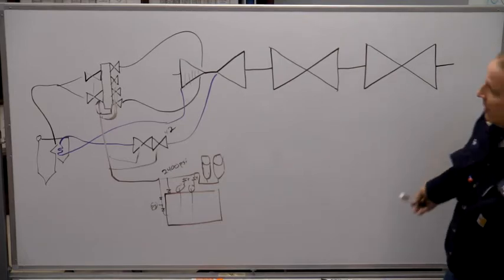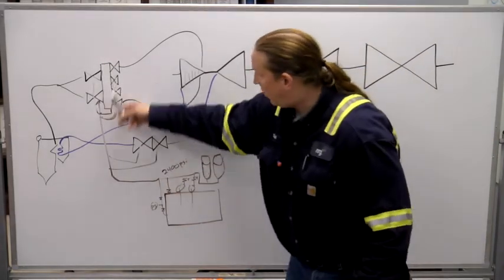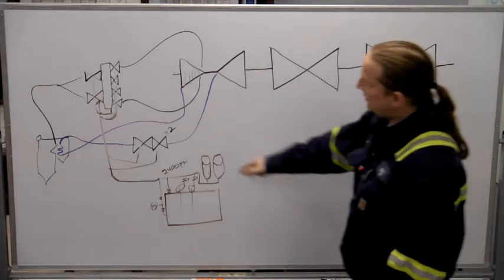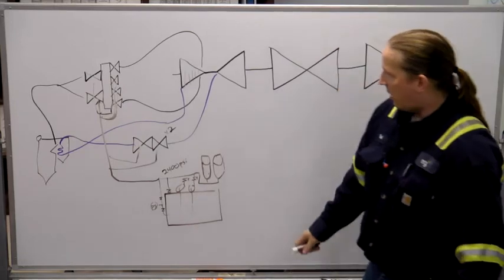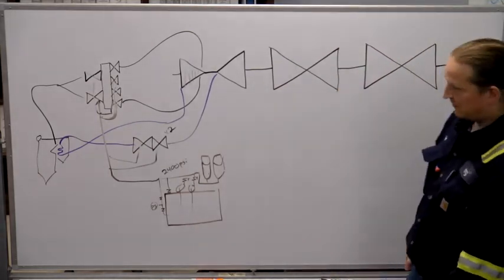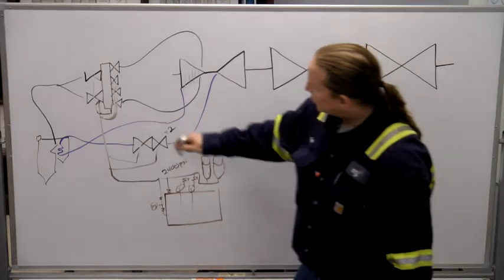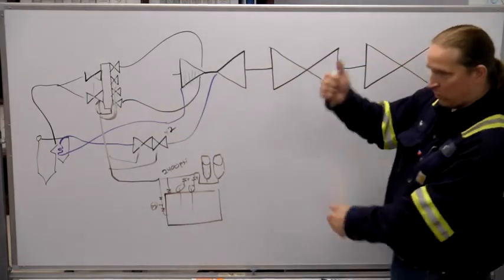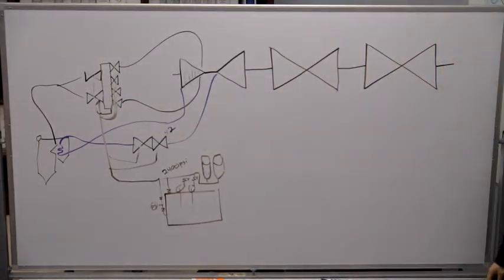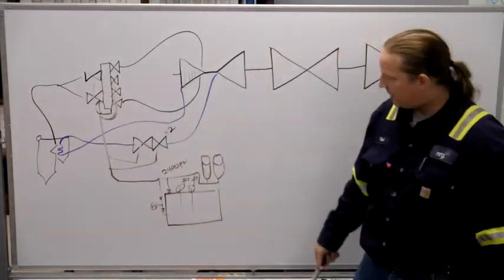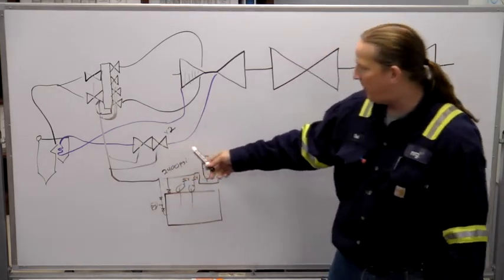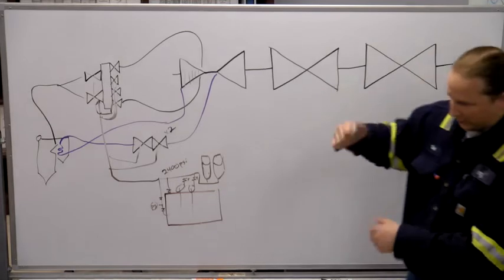If the breaker tripped, it should have tripped the turbine and all of those valves should have already gone shut — things take time. The main steam stop valves are oil to open, spring to shut. The control valves are piston — oil to move in either direction. The intercept valve stop portion is oil to open, spring to shut, and the control valve portion is oil to move in either direction.